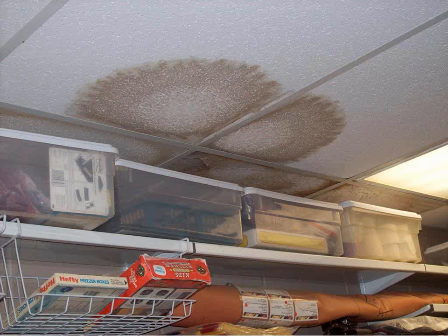And who knows, it looks like this has been dripping. If it's dripping into containers, these containers will probably hold water. They can grow mold. So obviously what needs to be done here is that the roof needs to be repaired. Someone needs to be brought in and figure out where the leak is happening. It's got to be repaired. The key to solving a mold problem is addressing the moisture problem. And probably of all the things that can damage a school, it's uncontrolled water in a school building, either from leaky roofs or leaky plumbing or condensation on cold surfaces or groundwater coming up.